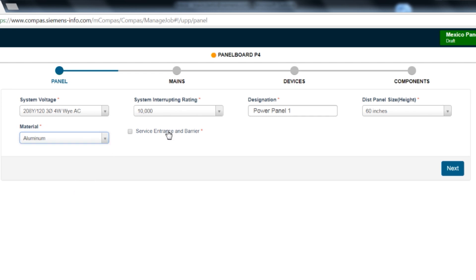The final selection is service entrance and barrier. This selection is needed for service entrance equipment with main breakers. Underwriters Laboratory and the National Electric Code require a barrier on service entrance main breakers to prevent inadvertent contact with the line side of the main circuit breaker with cables installed. This selection will allow the configurator to call out the correct service entrance barrier. After you have configured the base panel configuration selections, click the next button to go to the main configuration screen.